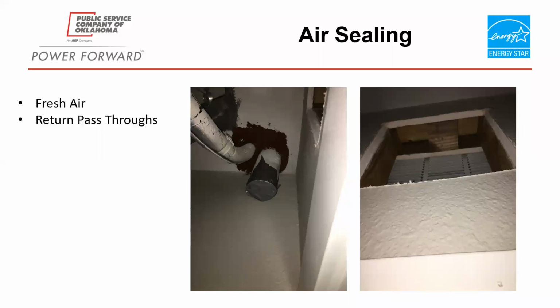The one on the right is a passive vent that goes from the living space to the combustion appliance zone - that's where the water heater or furnace live. The reason for this vent is so those combustion appliances will pull air, burn it, and push it up through the flue pipe. The problem is, when it's coming in that way, that air is communicating back and forth with the inside of the house. As you can see, there's a massive gap between the two pieces of sheetrock, and that space goes all the way up to the ceiling or the attic.